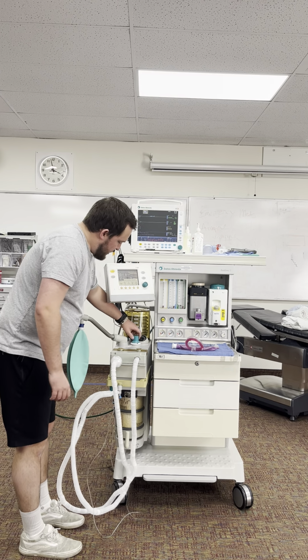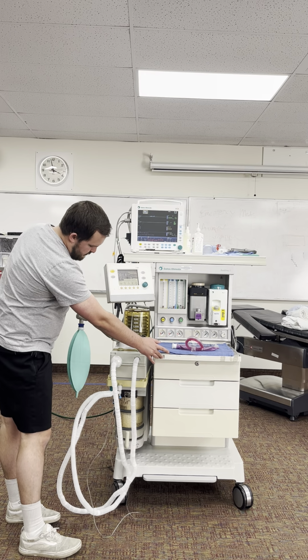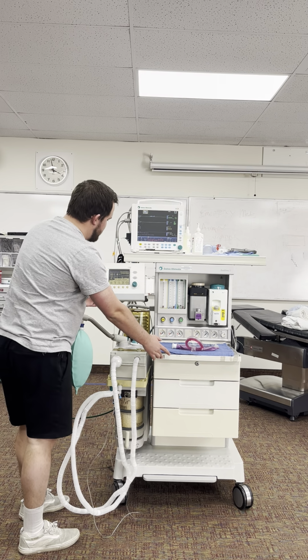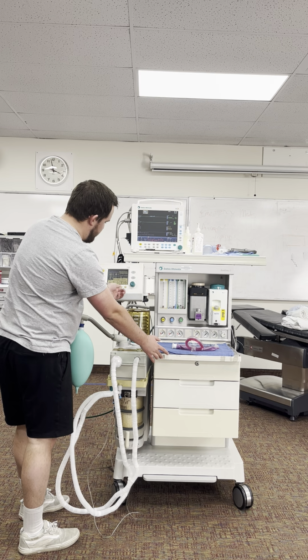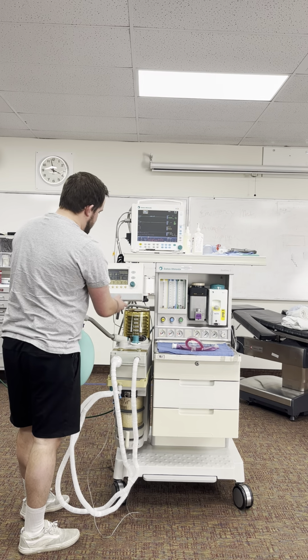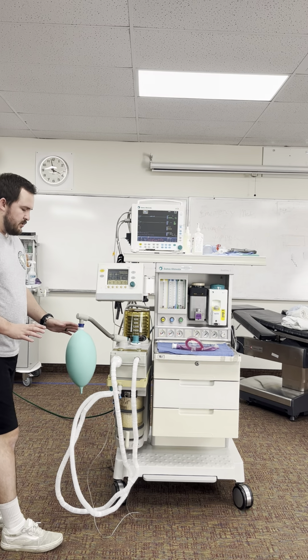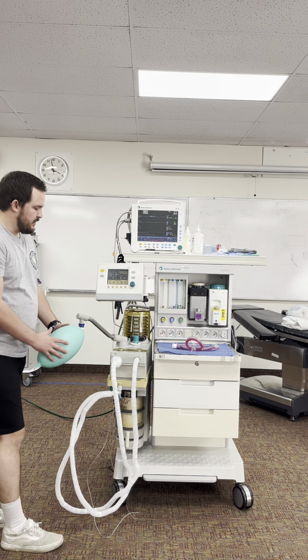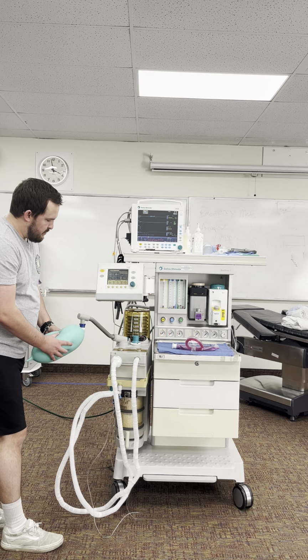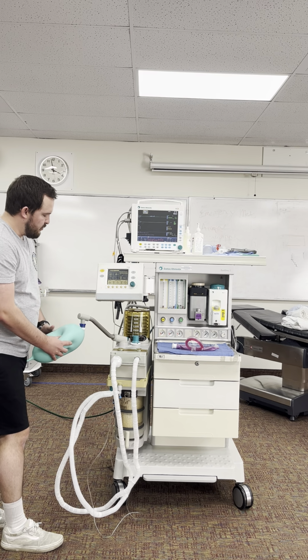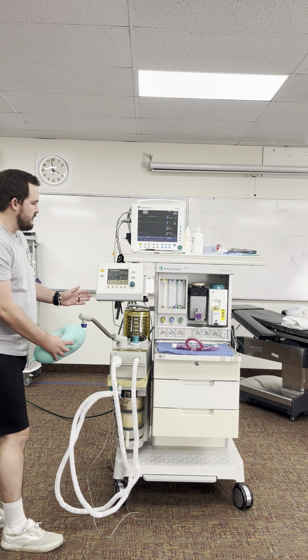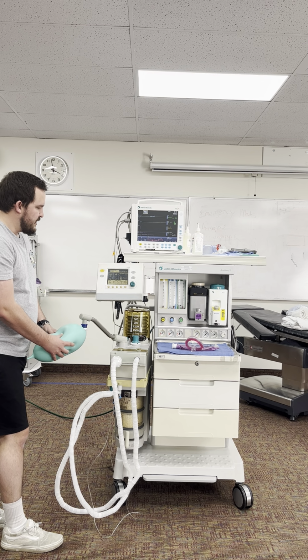Now I'm going to do my high pressure check. I'm going to use this. I'm going to increase the pressure until I get up to a pressure of 30, which is where I'm at. I'm gonna sit here and maintain, which is just making sure that there's no leaks in the internal system. Now I'm gonna check my alarm, putting it up above 40. We hear it alarming. And we're gonna wait one more just for the sustained alarm.